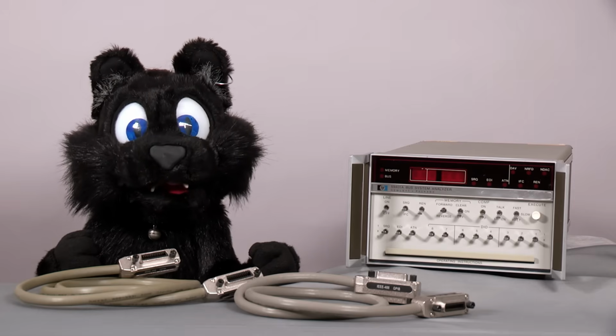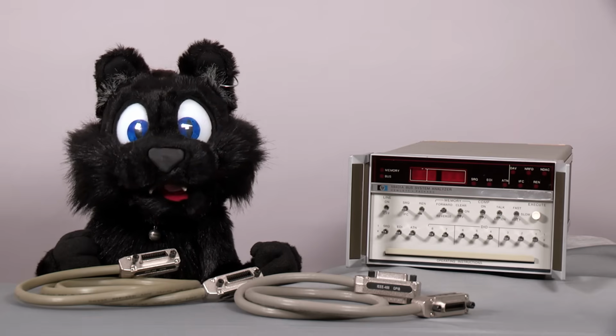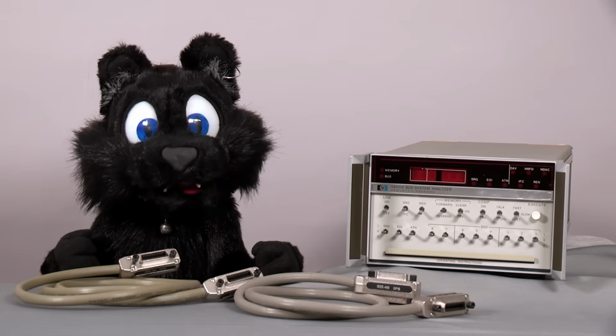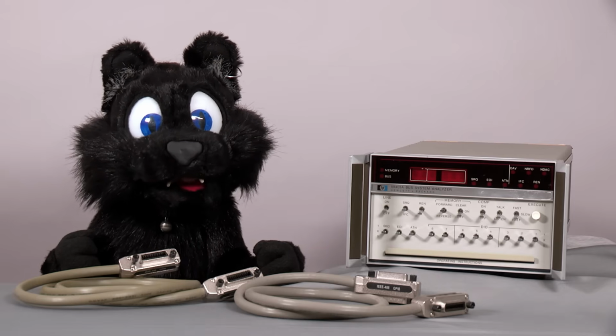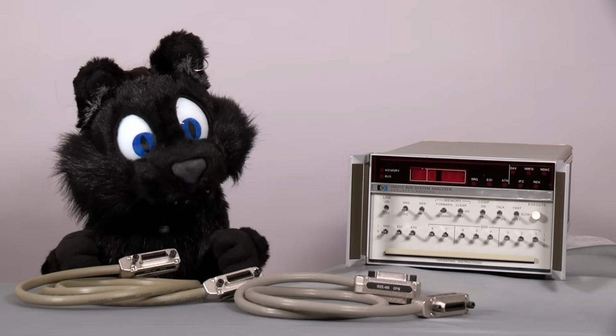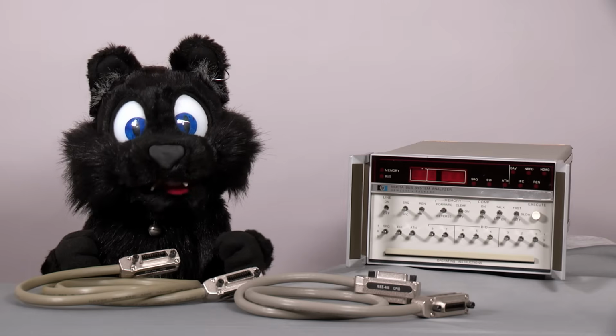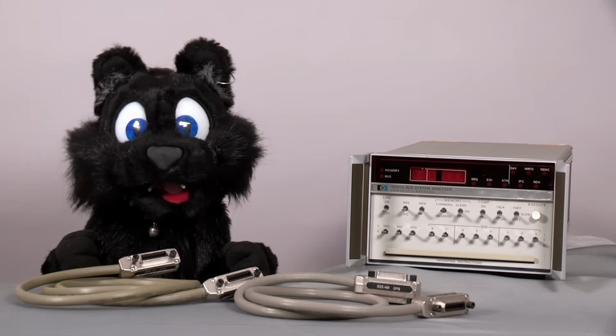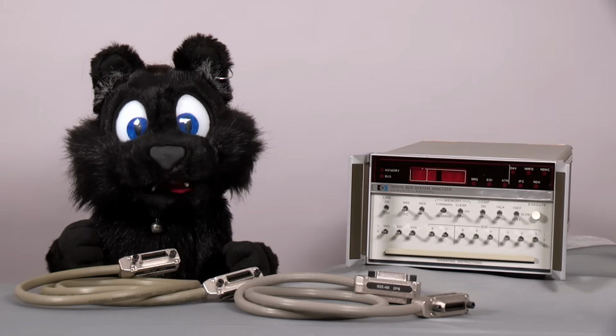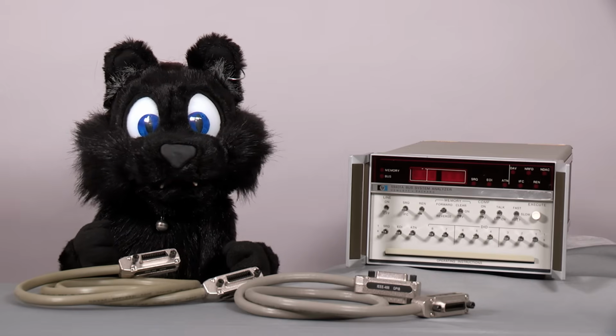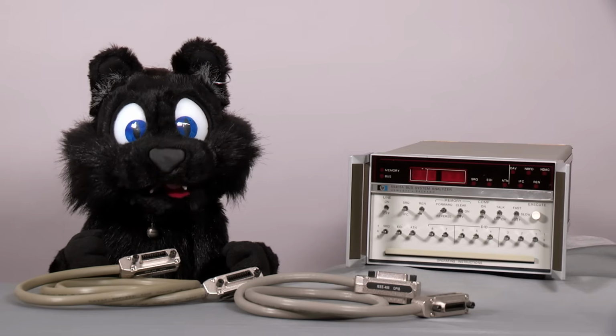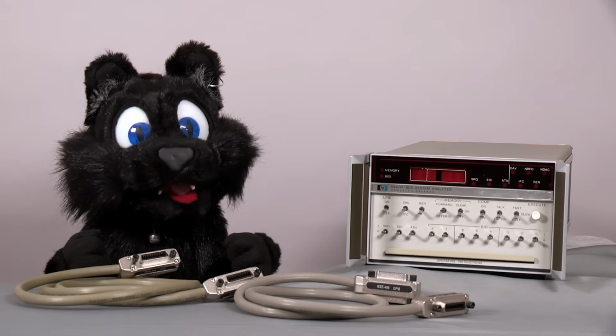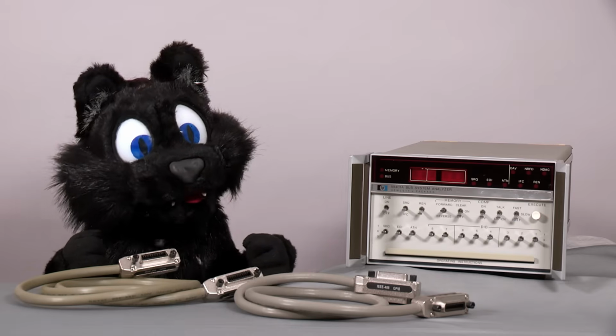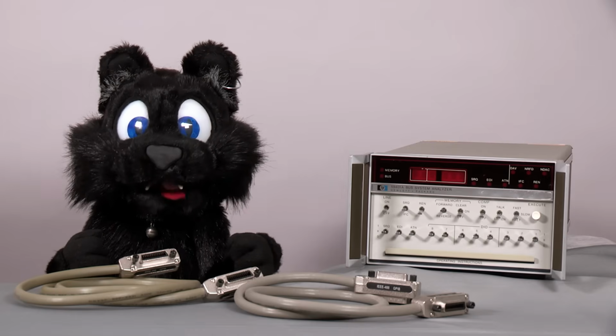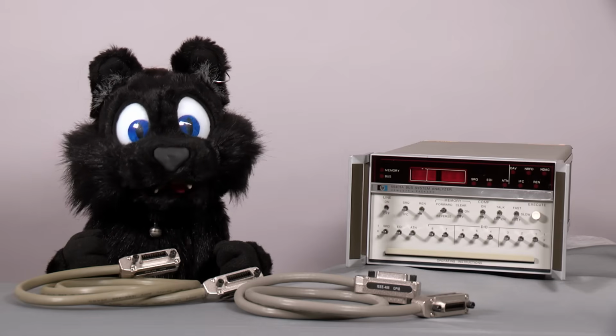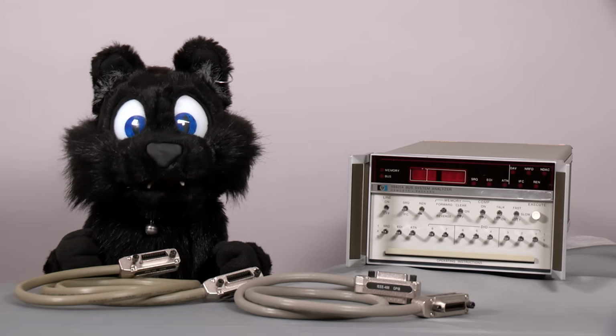GPIB is a rather old and slow way of connecting digital equipment developed during the 1970s. It is an 8-bit parallel bus that runs at TTL levels and can connect up to 15 devices on the bus. The cables use a 24-pin connector that stacks male and female ends in one case, making daisy chaining easy without needing separate in and out sockets like SCSI has. In the early days, HP used the bus for all sorts of computer peripherals like tape drives and printers, but over time faster alternatives were introduced. Test instruments are pretty much the only device category left that still uses GPIB today, but USB and Ethernet are displacing it here too.